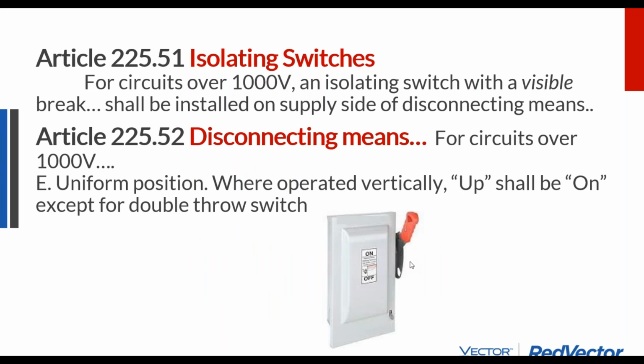So then we get into some switch specific requirements, like isolating switches that say for over 1,000 volts, the switch needs to have a visible disconnect, which means that you can look inside of it and actually see where the disconnecting point is made. So a breaker, you can't see inside a breaker. That's not a visible break. It doesn't mean a viewable break. They make these switches with a little plastic window so you can look inside and see it working without taking the cover off. A visible break means you can take the cover off and look inside and see the disconnect being made.